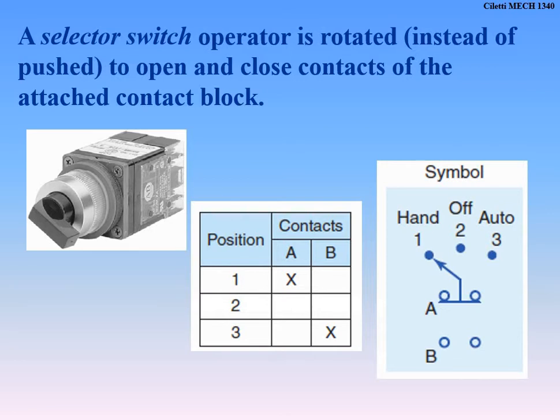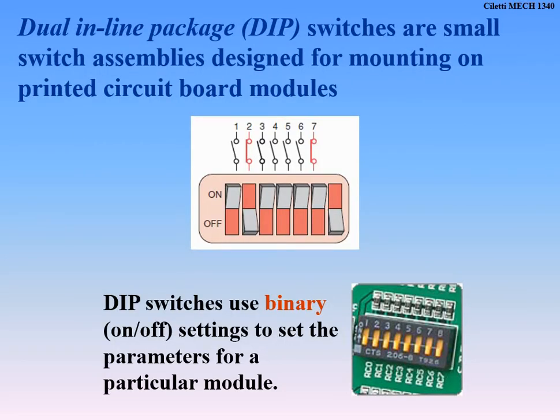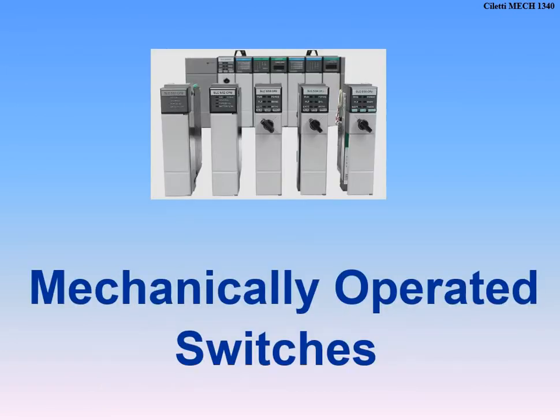Manually operated switches include push buttons: green is typically a normally open start button, and red is a normally closed stop button because pushing it must break the circuit to stop things. There are also selector switches — on the 870 trainer we have manual, auto, and reset positions. A selector switch in auto lets everything run freely; in manual, you step through each stage manually. DIP switches (dual inline package) are just binary switches sending strings of zeros and ones.